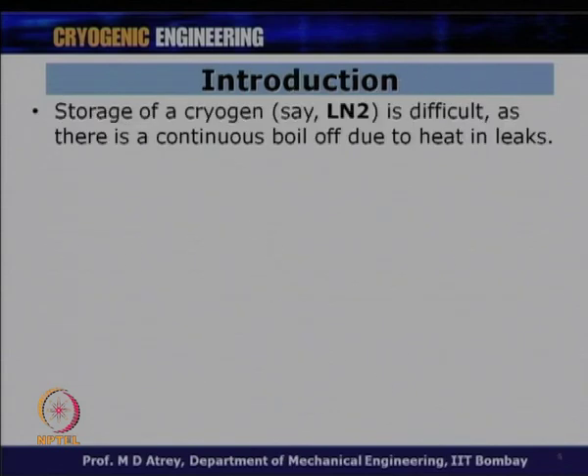As an introduction to why we need cryogenic insulation: we are talking about very low temperatures, around 77 Kelvin or 4.2 Kelvin, while our ambient temperature is normally around 300 Kelvin. There is naturally heat transfer from high temperature to low temperature, so we will always have heat in-leak from outside to inside. Our fundamental task is to reduce this heat transfer from 300 Kelvin ambient to the cryogenic temperatures. We should have insulation to prevent these heat in-leaks, and while we cannot make it equal to zero, we must minimize it.